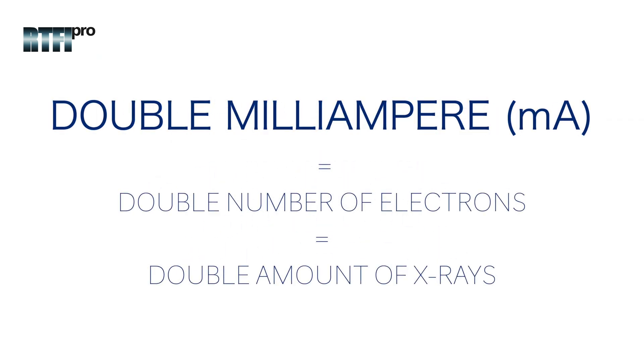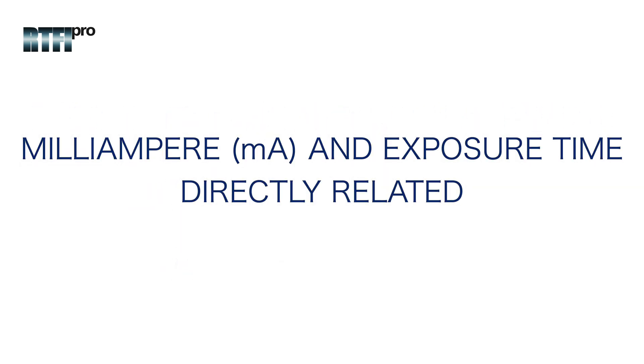As a result, if the milliampere is doubled, it will double the number of electrons and therefore double the amount of x-rays produced. If the milliampere is reduced to 50% of the original MA, it will reduce the number of electrons traveling to the anode target by 50% and in turn reduce the amount of x-rays produced by 50%. As mentioned, milliampere and exposure time are directly related.